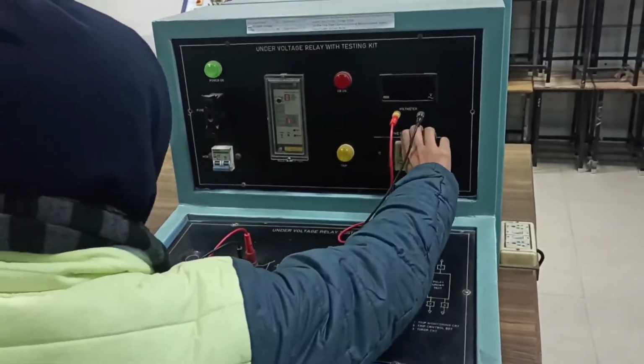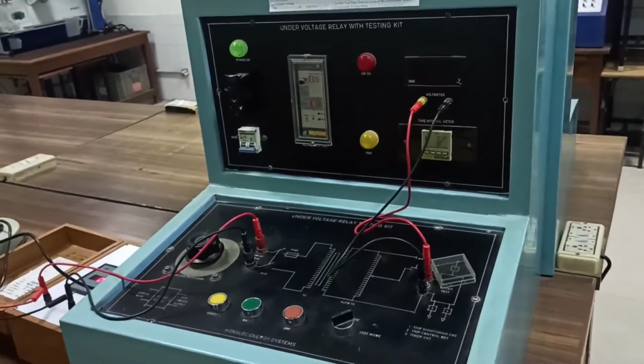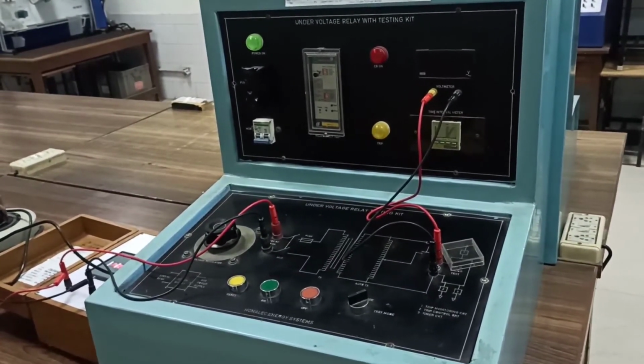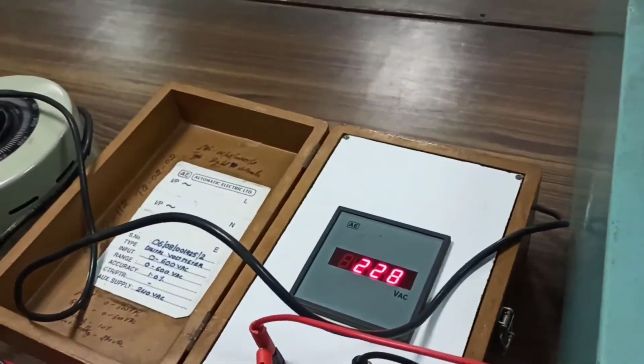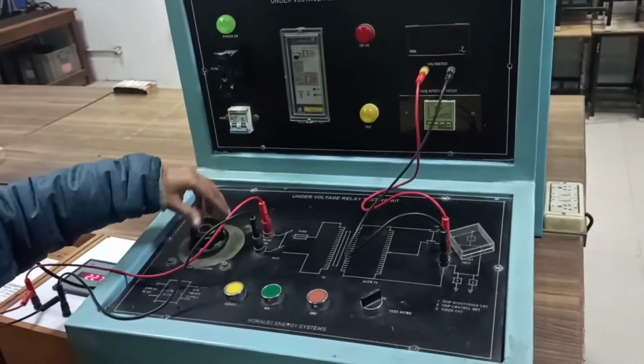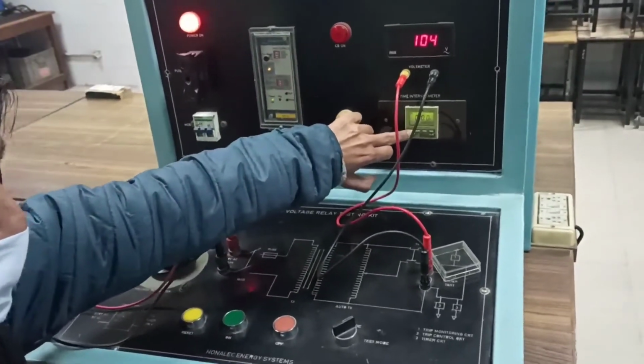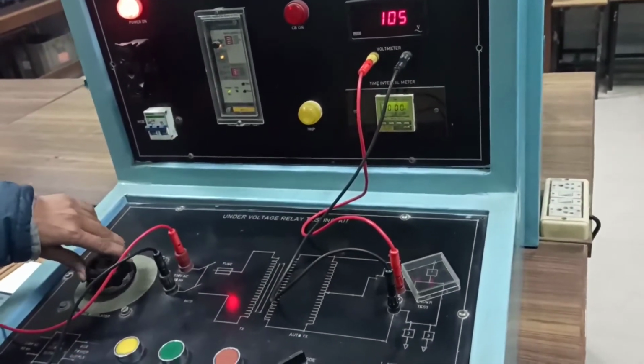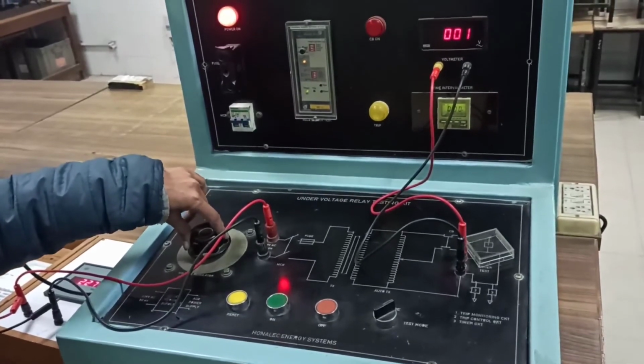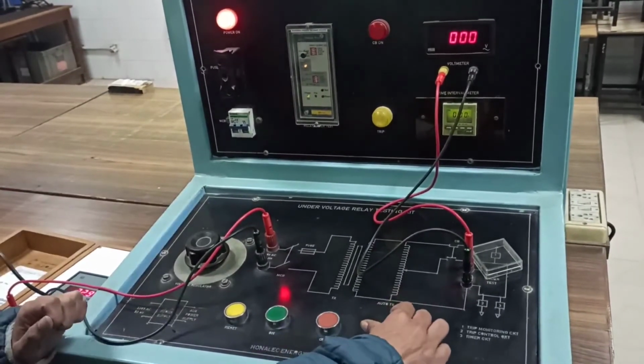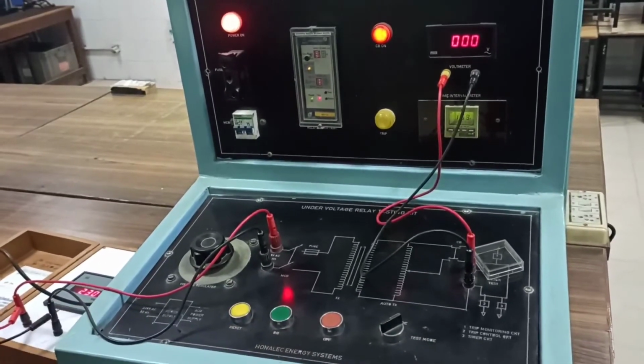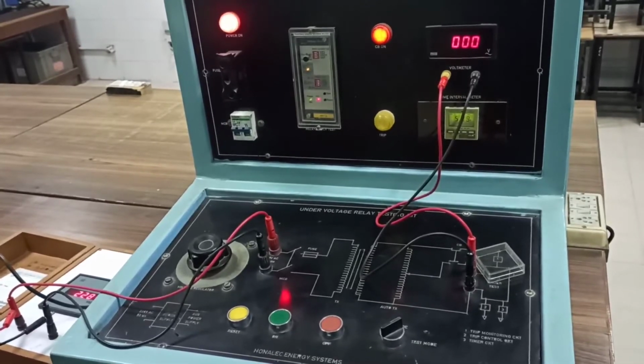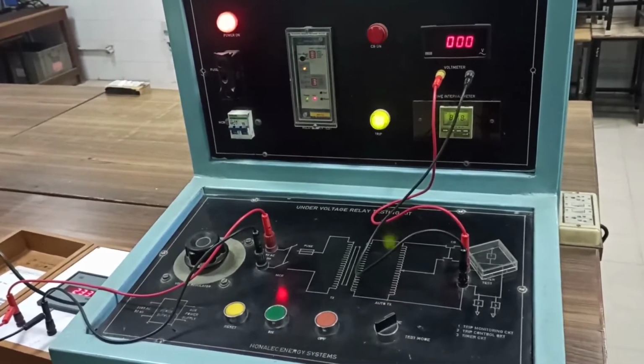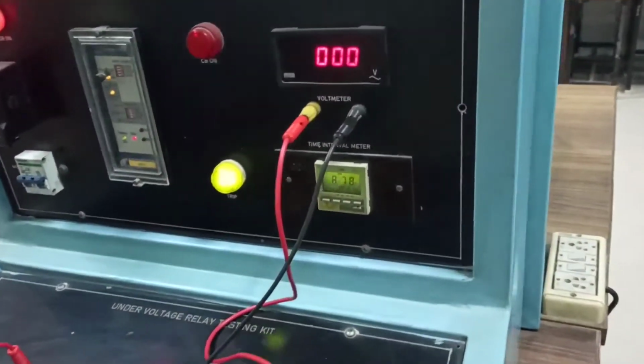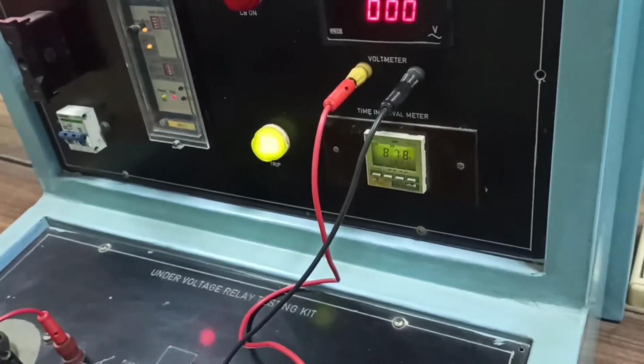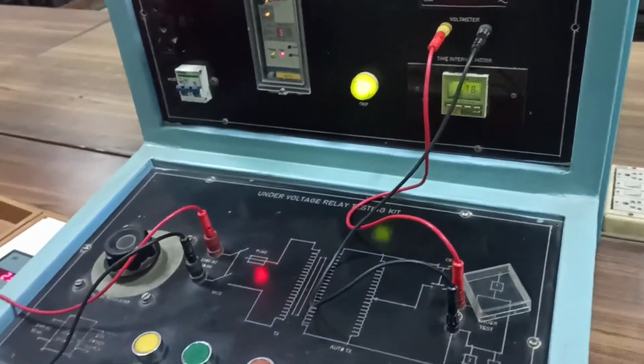The same experiment with under voltage. Again set the supply voltage to 230 volt. Switch on. Set the timer at 90 seconds. Set the fault voltage to the minimum, at 0 volt, for under voltage. Now set this switch to test mode. Switch on again. At zero volt, the trip time is 8.78 seconds. This is the time taken by the relay to operate the circuit breaker. Now again reset it.